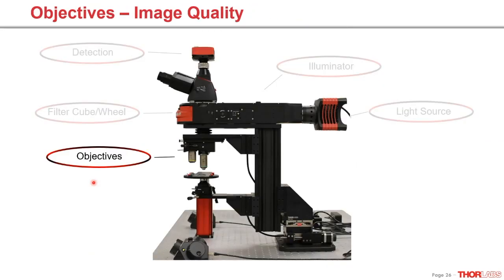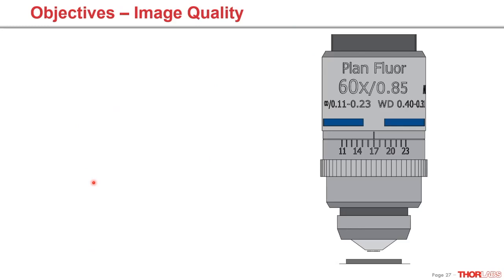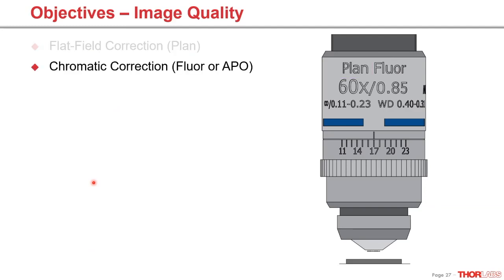Objectives are one of the most critical elements related to image quality, which has a lot to do with aberration. When selecting an objective, look at aberration corrections. 'Plan' marked on the objective means it has flat field correction — it's aberration-free across the field of view, so you won't have distortion at the edge. Next is chromatic correction, termed 'Fluor' or 'Apochromat'. When multiple colors are involved, you want them optically and physically lined up so you don't have chromatic aberration — meaning no lateral or axial shift between colors even though they travel slightly different light paths.